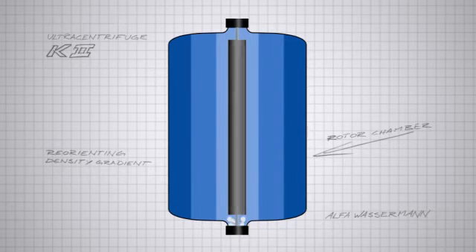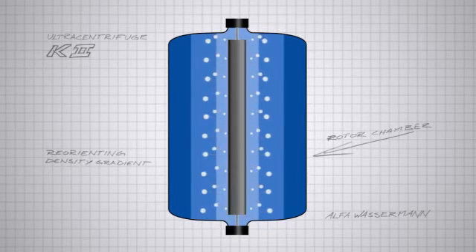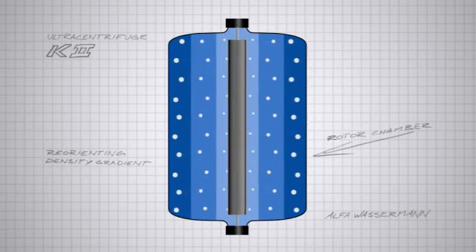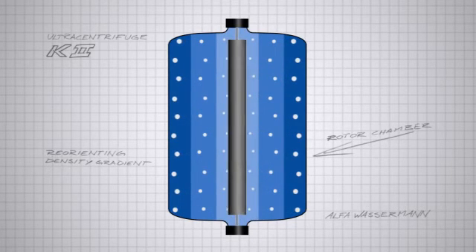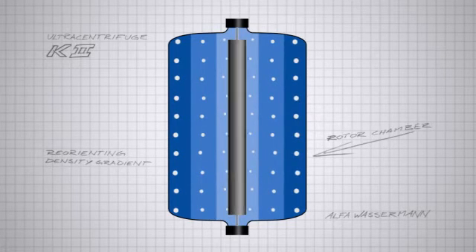Sample fluid is then pumped into the rotor in a continuous flow mode, and the sample particles begin to sediment radially. The sample particles will band within the zone where the gradient density equals the particle's buoyant density.